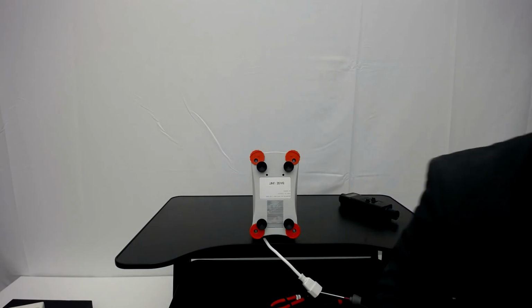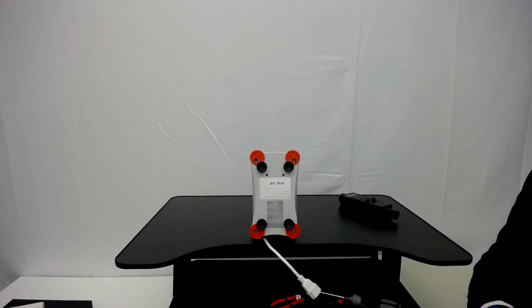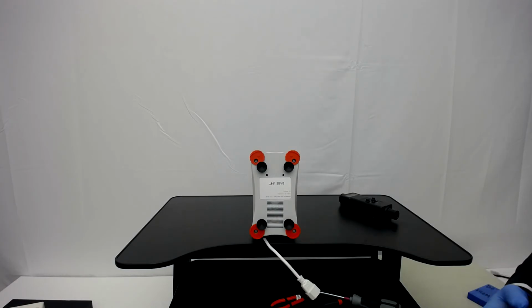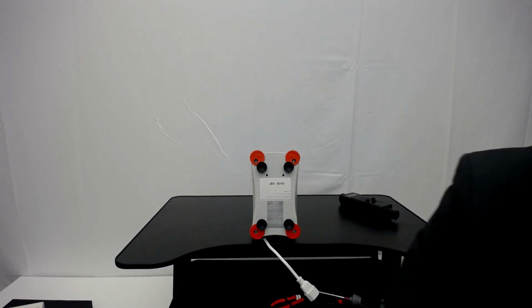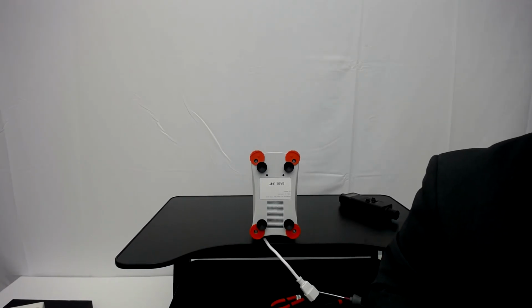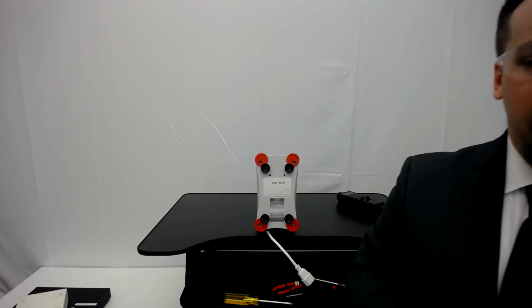All right, so that is our mini vortexer repair training. We've basically gone through the calibration. There is a pre-pack procedure that you can do, but it's very simple, very much like what we've seen. So you can get that directly from the service manual. And as with any other unit, we're going to do a high pot test every time we open and close the unit to make sure that there is no electrical hazard to the user.